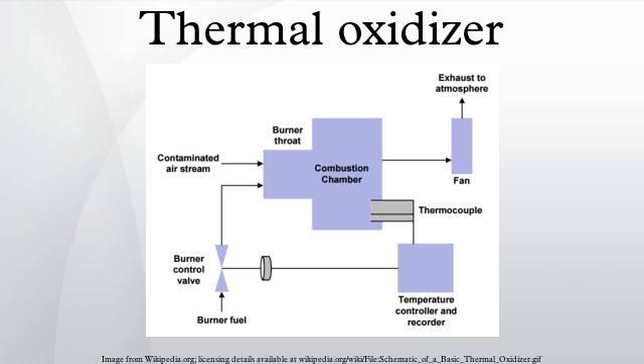Most direct-fired thermal oxidizers operate at temperature levels between 980 degrees Celsius and 1200 degrees Celsius with air flow rates of 0.24 to 24 standard cubic meters per second.